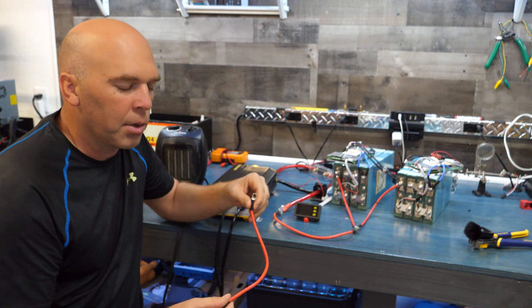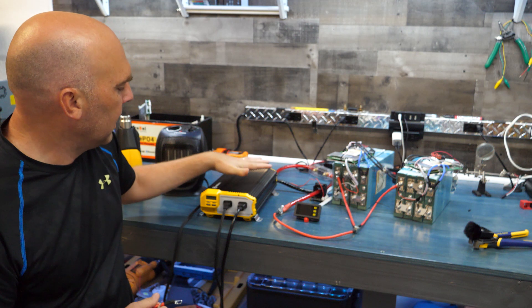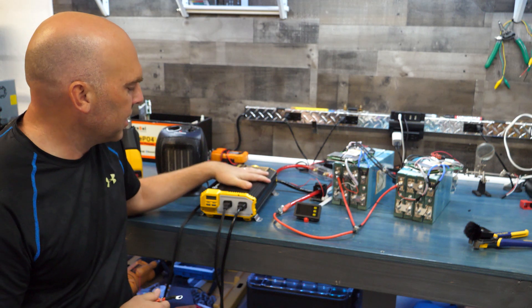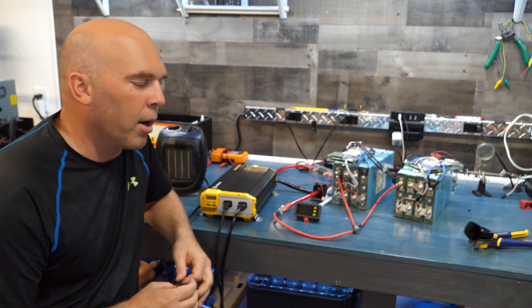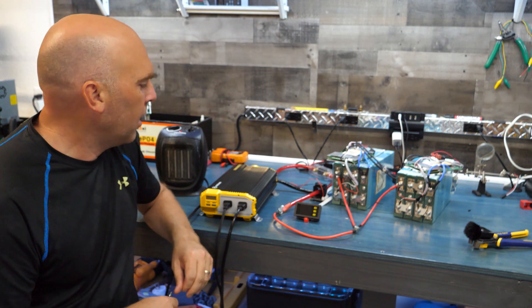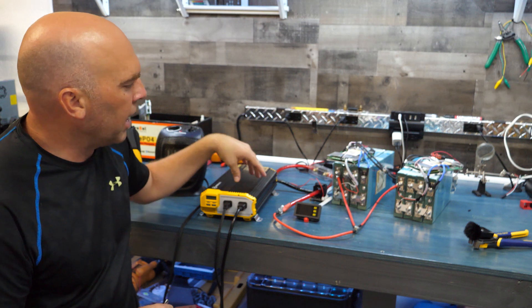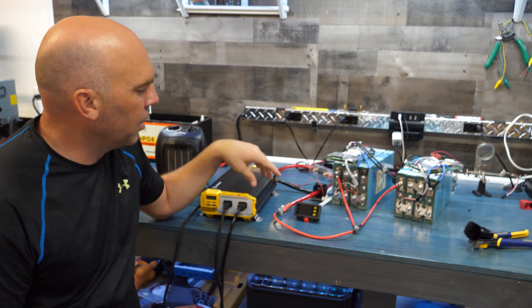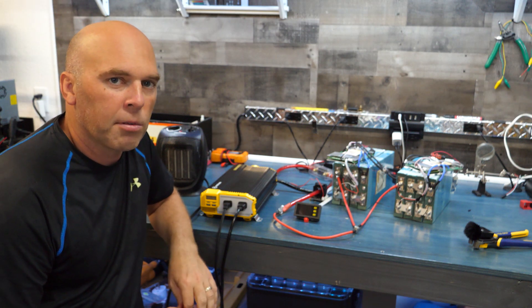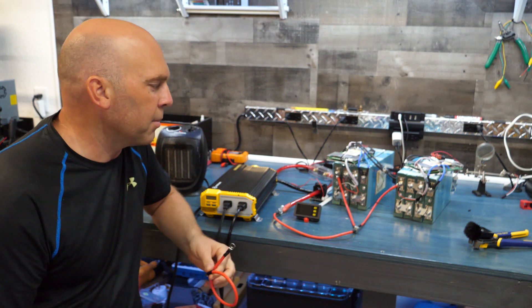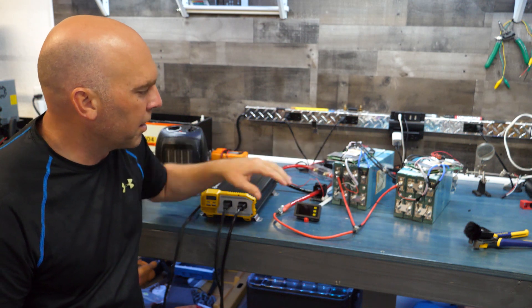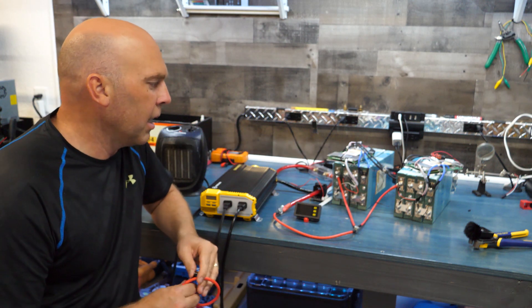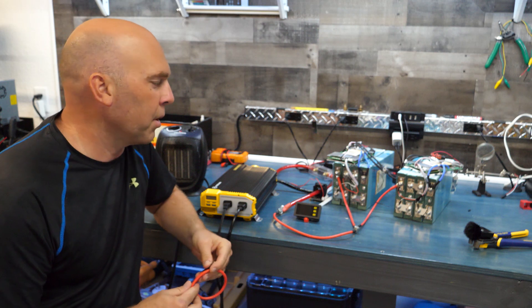So that's kind of the backstory on what we're doing here. We're going to test this up to about 115 to 120 amps, and only because that's about as much as I can get out of this Krieger 1500 watt inverter before it goes into shutdown mode. Also because our batteries are limited through the BMS to not go over 110 amps. If they go over 110 amps for greater than 10 seconds they cut off for 32 seconds.